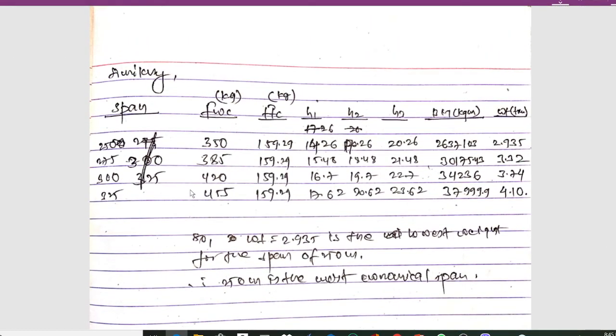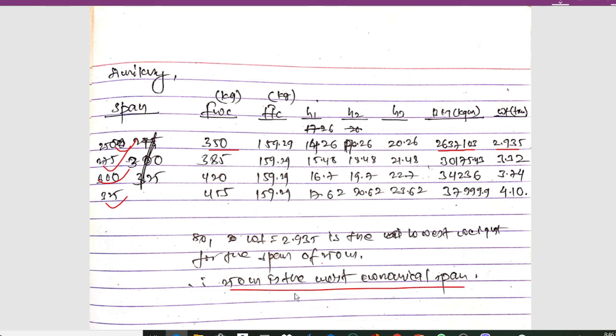Tabulating the results: for 250-meter span, Fwc = 350 kg, bending moment = 263710.3 kg·m, and weight = 2.935 tons. For 275-meter span, weight = 3.32 tons. For 300-meter span, weight = 3.74 tons. As span length increases, the tower weight also increases. Therefore the minimum weight of 2.935 tons corresponds to the 250-meter span, making 250 meters the most economical span.